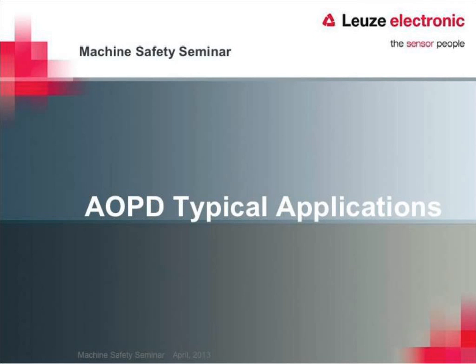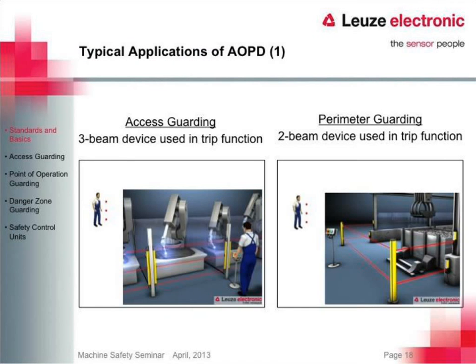Now we'll look at some typical AOPD applications. An AOPD — active optoelectronic protective device — is typically a light curtain, multi-beam, or safety scanner. There are three typical applications: access or perimeter guarding, danger point guarding, and danger area guarding. For perimeter guarding, we would use a multi-beam. It needs to be far enough away from the hazard that we don't have to worry about depth of penetration issues. We're basically looking for a trip device to make sure nobody walks into the area. We can do it cheaper with a multi-beam than a light curtain because it uses fewer optics, and we can go farther distances, making a big perimeter around the entire dangerous area with one device bounced off a couple of mirrors.